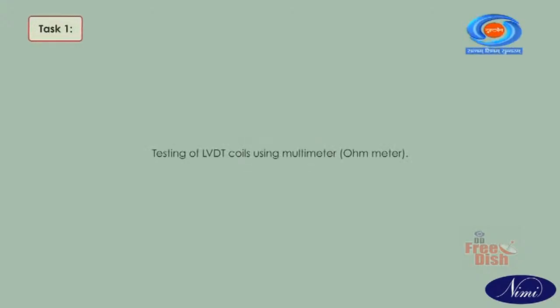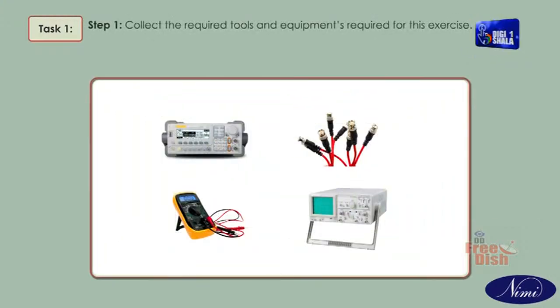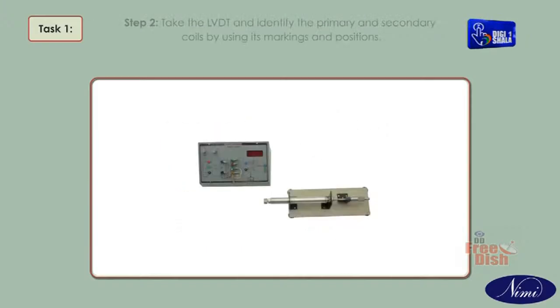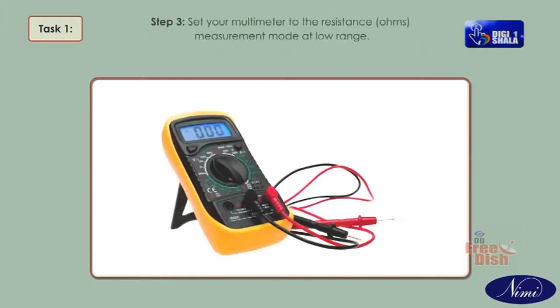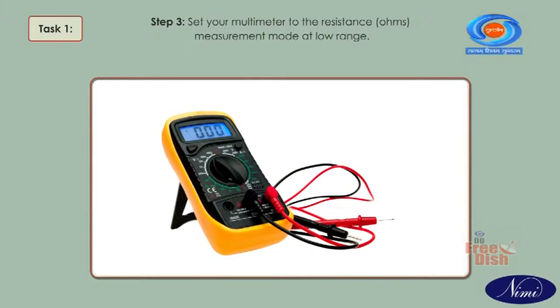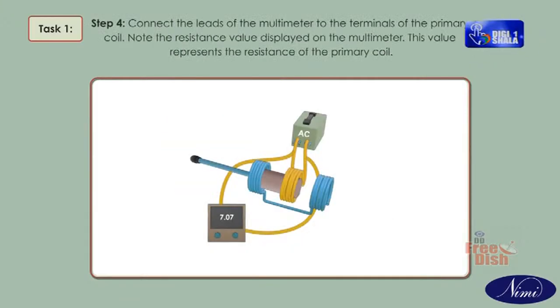Procedure. Task 1. Testing of LVDT coils using multimeter, ohmmeter. Step 1. Collect the tools and equipment required for this exercise. Step 2. Take the LVDT and identify the primary and secondary coils by using its markings and positions. Step 3. Set your multimeter to the resistance, ohms, measurement mode at low range. Step 4. Connect the leads of the multimeter to the terminals of the primary coil.